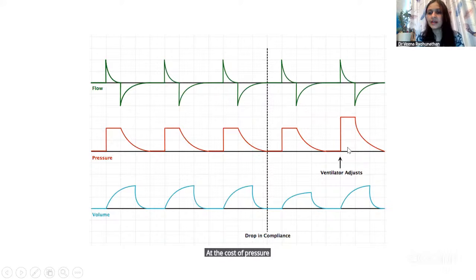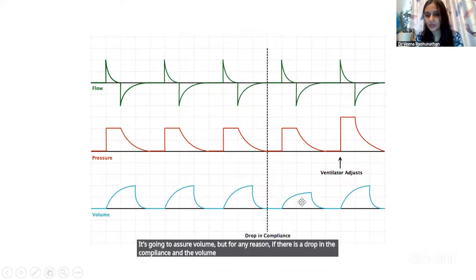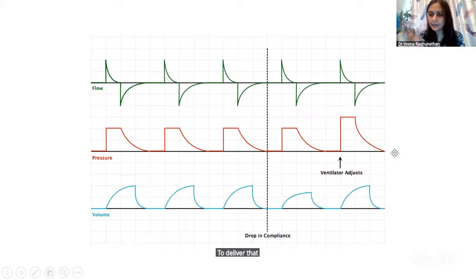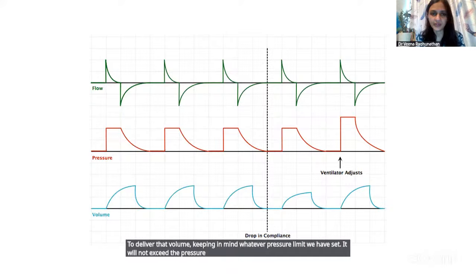So pressure might go up. It can go up to whatever pressure limit we have set. So that is the PRVC mode. It's giving flow in decelerating form. It's going to assure volume. But if for any reason there is a drop in the compliance and the volume delivery gets compromised, it will increase the pressure in the next breath, subsequent breaths, to deliver that volume, keeping in mind whatever pressure limit we have set. It will not exceed the pressure limit that we have set.